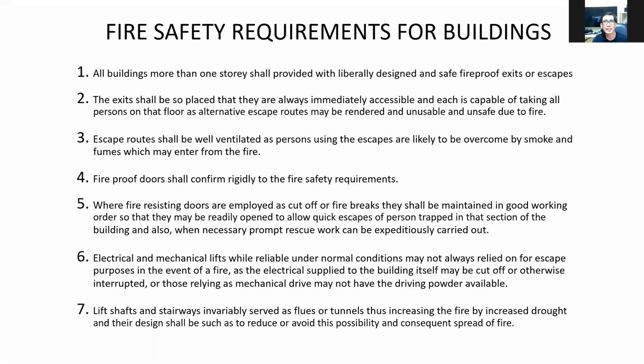Lift shafts and stairways invariably serve as flues or tunnels, increasing the fire by increasing draught, and their design shall be such as to reduce or avoid this possibility and the consequent spread of fire. So the stairs are the conduit of smoke, no, to transfer it from one floor to another. It's a main conduit of smoke. So if your stairs are not properly isolated from other areas of the building or the floor, the smoke will pass through a stair or a shaft that will enable the smoke to go to other areas of the building. Even the heat from the fire can pass through the stairs and the elevator shafts. Okay.